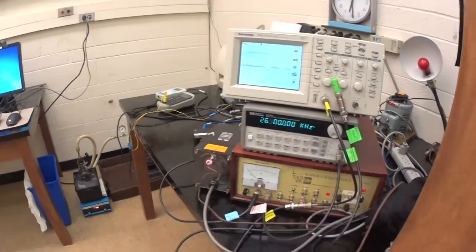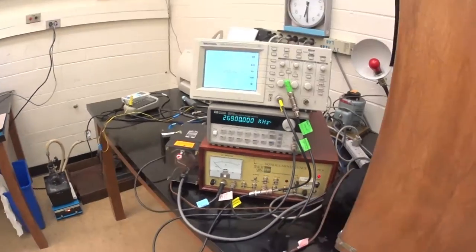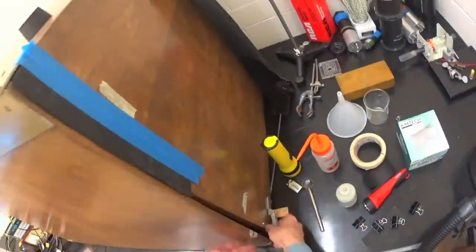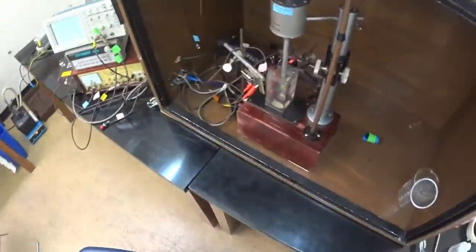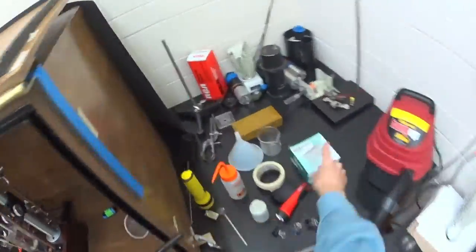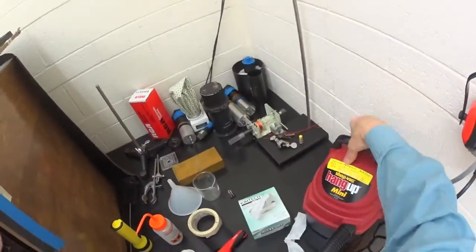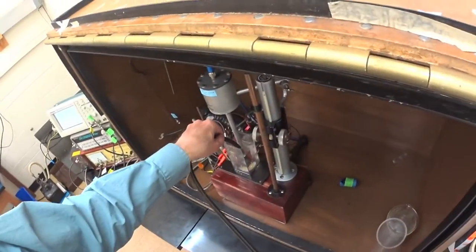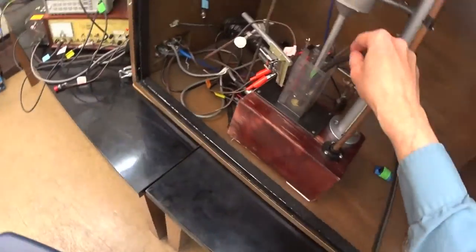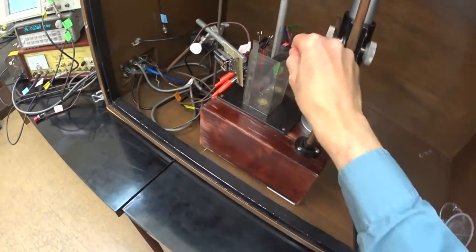Turn off the PMT power. This is important. If you forget, you may fry the PMT. Slowly unfasten and open the door. Keep an eye on the oscilloscope since channel 2 will go crazy if you've forgotten to turn off the PMT power. Suction the water out of the cell using our handy mini wet-dry vacuum cleaner. Take the vacuum cleaner to our large sink to empty it out if it feels full.